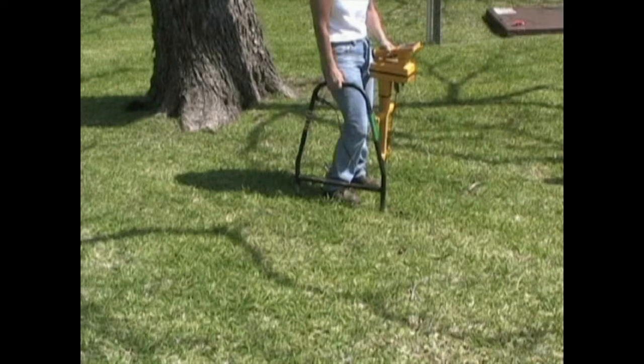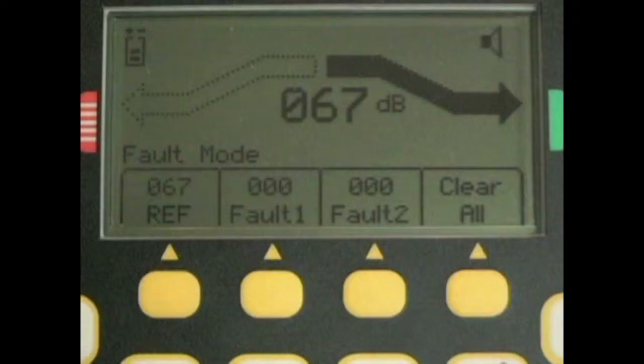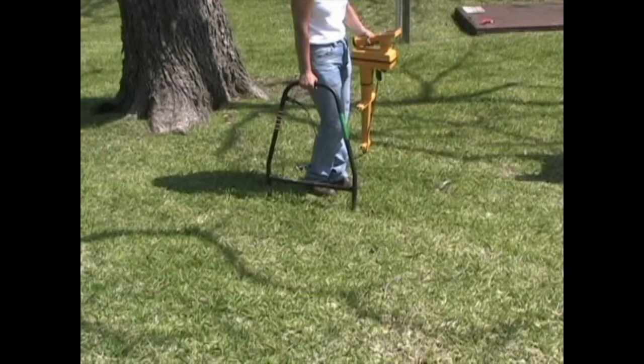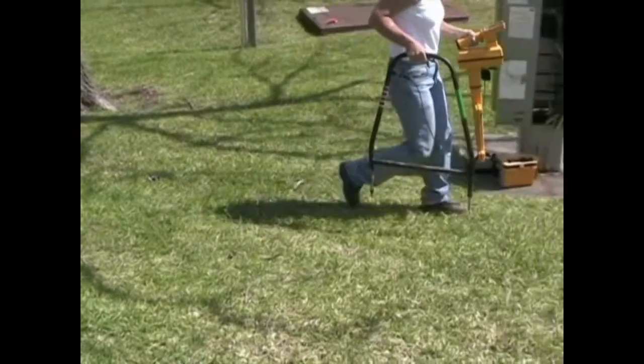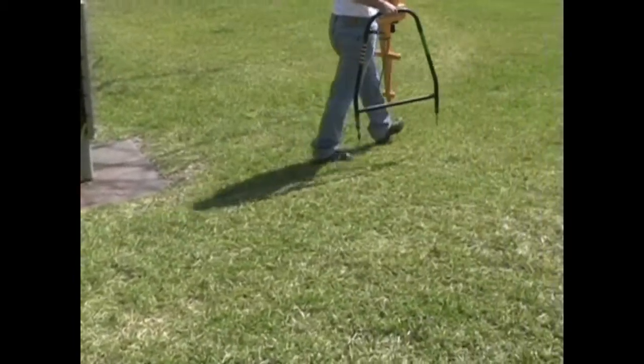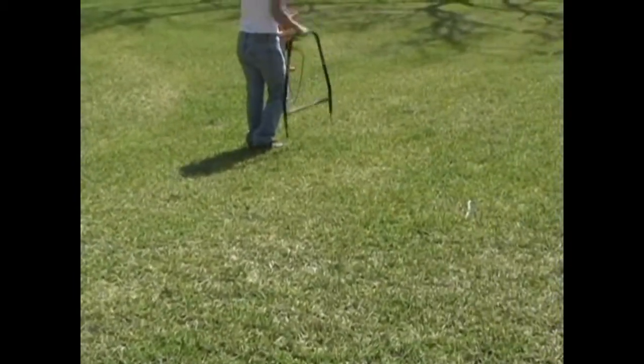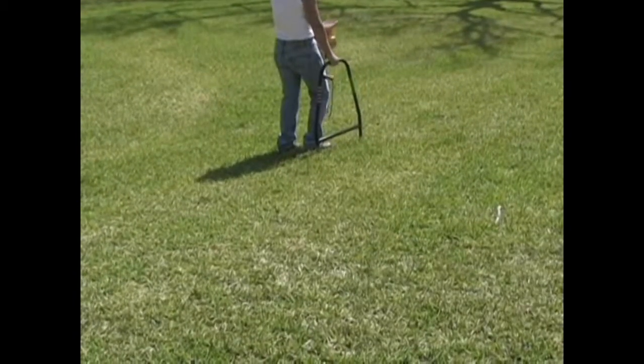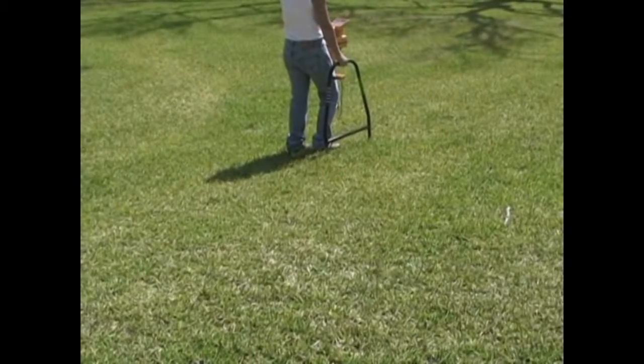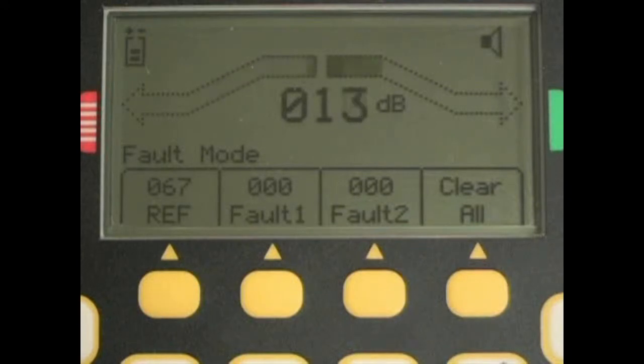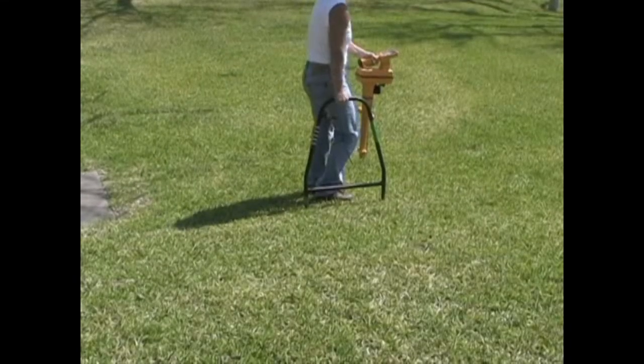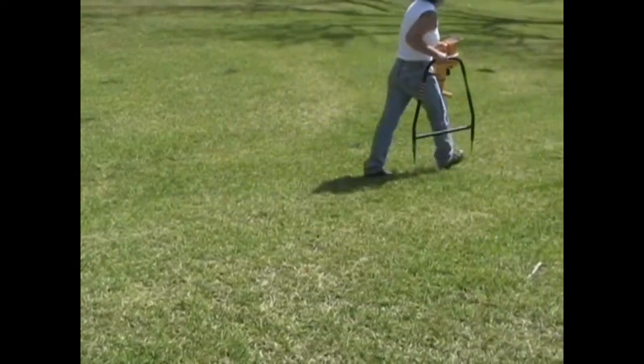With the A-frame still inserted at the reference point, you will notice on the receiver that an arrow fills the screen toward the green band on the right side of the receiver. This is the indication that the fault is closer to the green leg of the A-frame than the red leg. Move the A-frame forward toward the green leg. Insert it into the ground again. Let the signal strength settle on the screen, then move the A-frame toward the red or green leg indicated by the receiver. It is not necessary to probe the ground every few feet.